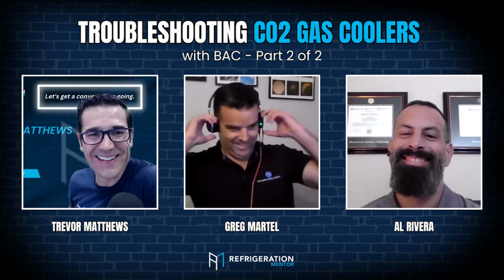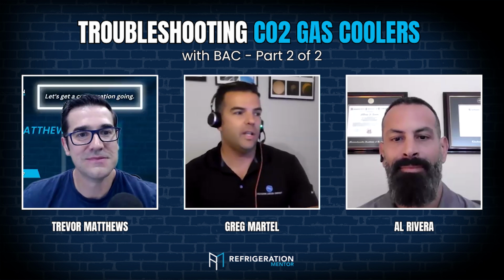No, so good answer. So honestly, like you said, I'm not a refrigeration technician. But one of the common calls that I get is that the condenser lost capacity. So it was working fine for 2 years, and now today it doesn't meet set point, and my head pressures are through the roof. So we have a case, and again, we could spend hours talking about this.